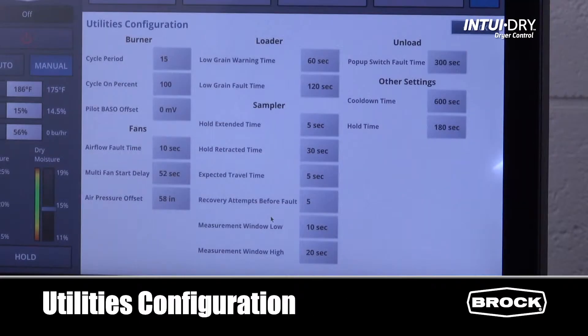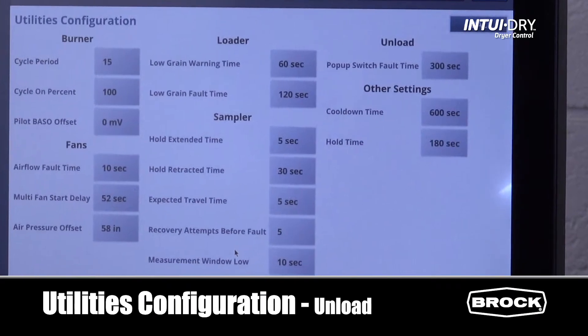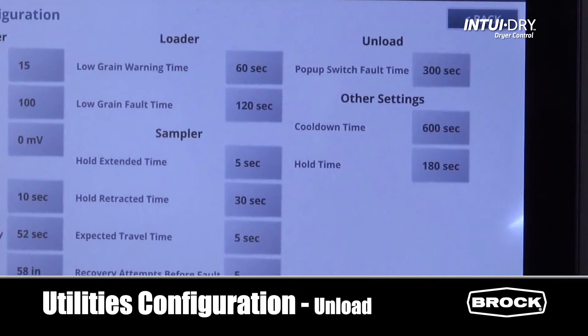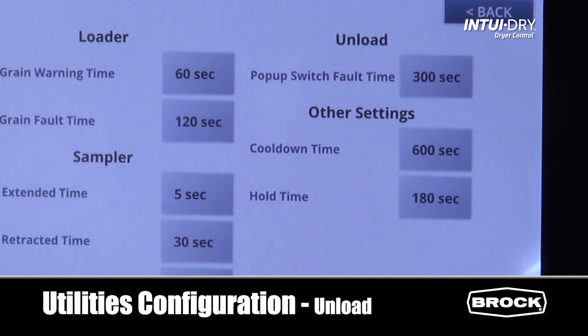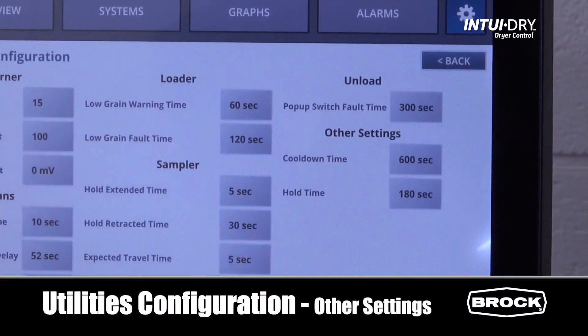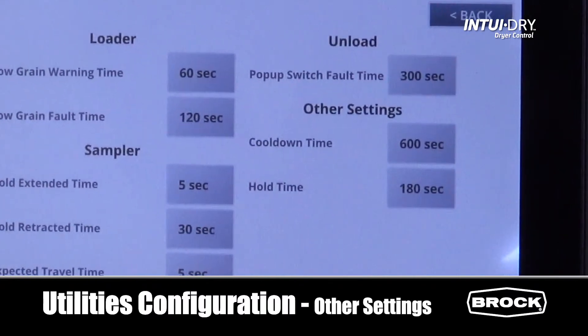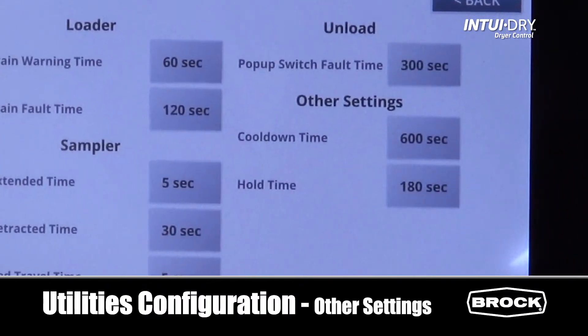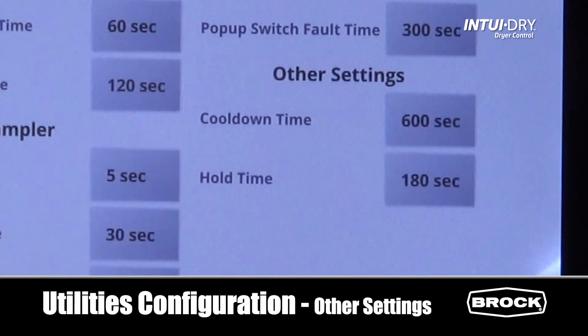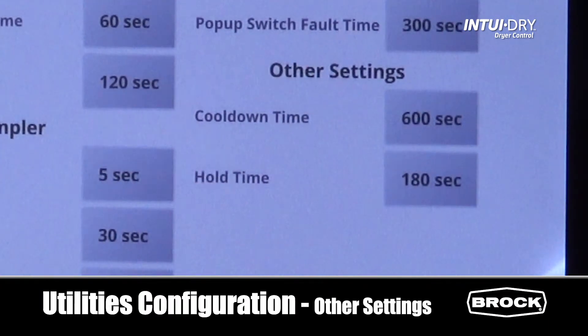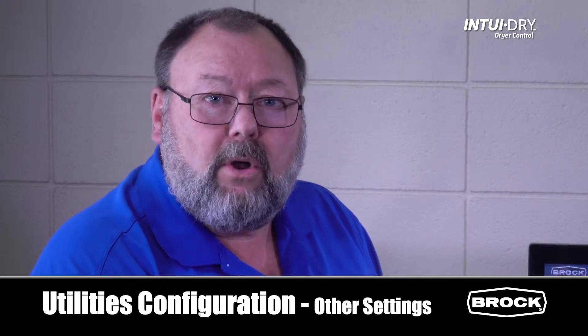The unload pop-up switch timer is the length of time before the grain dryer shuts down if the reclaim conveyor is not taking away the grain fast enough. The cool down timer is how long the fan runs after the burner shuts off to cool the grain down in the dryer. The hold timer is how long you have to resume the dryer after placing it on hold — if this timer times out, the dryer will go into shutdown and start the cool down timer.